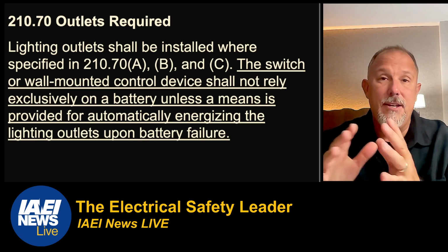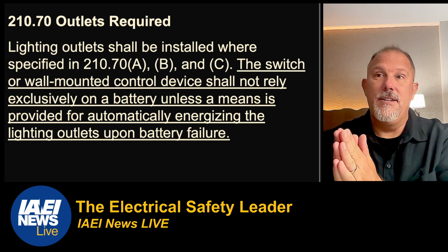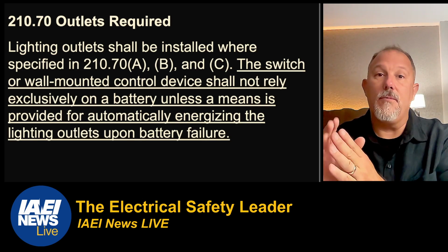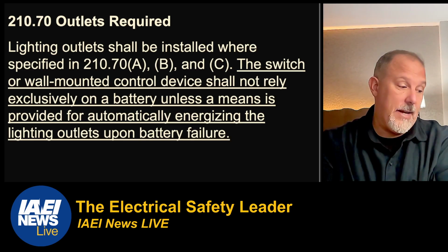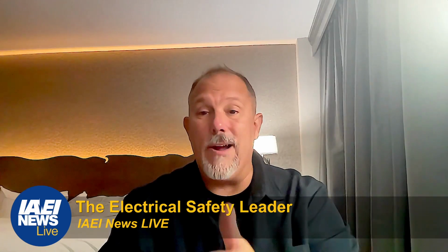But I think the underlying true concern really is there are many on the code panel that really want to pull a hard wire down to the light switch. So for a lot of different reasons. If I don't want it now and I want it later. And then keep in mind too that the scope of Article 404, which is switches, says the article does not cover wireless control equipment to which circuit conductors are not connected. So they didn't want any part of these wireless controllers.